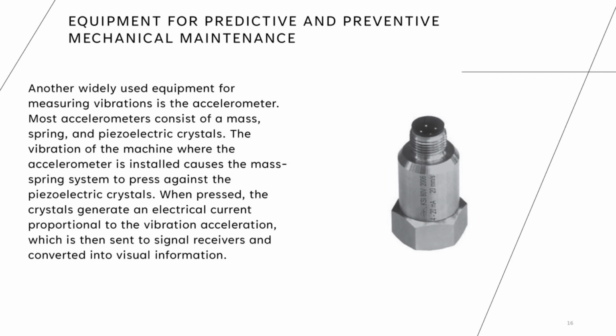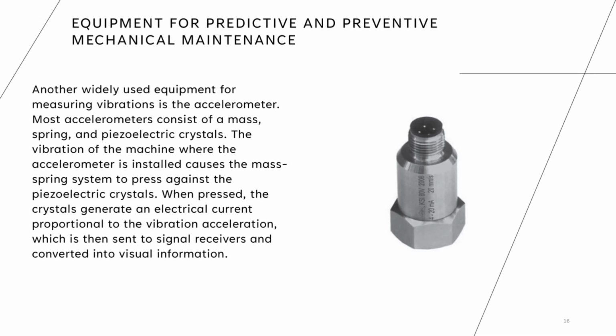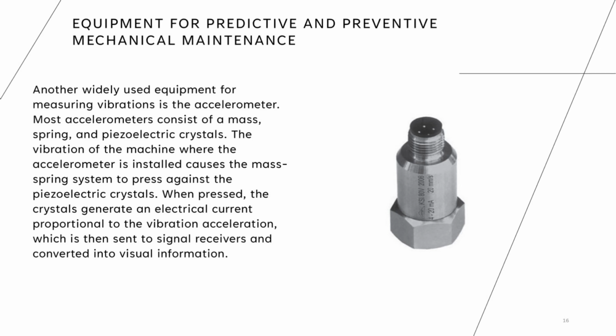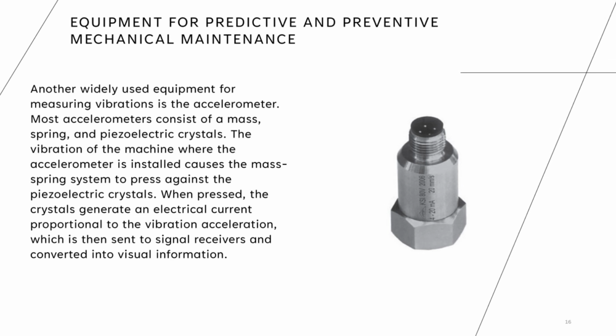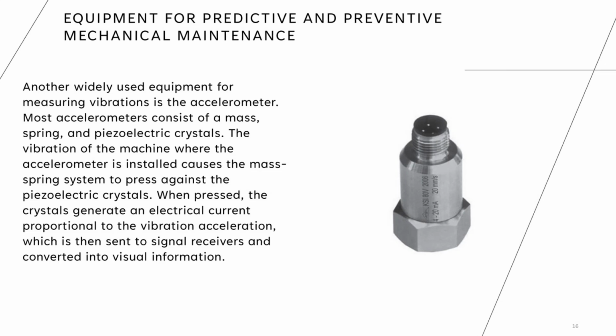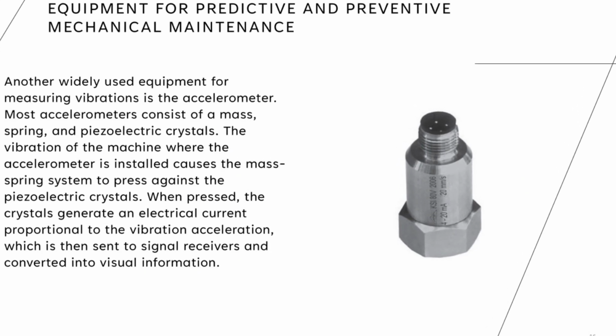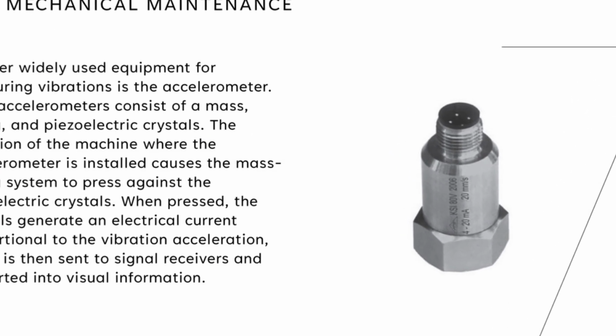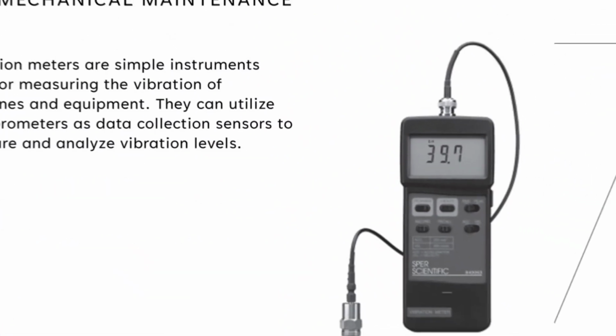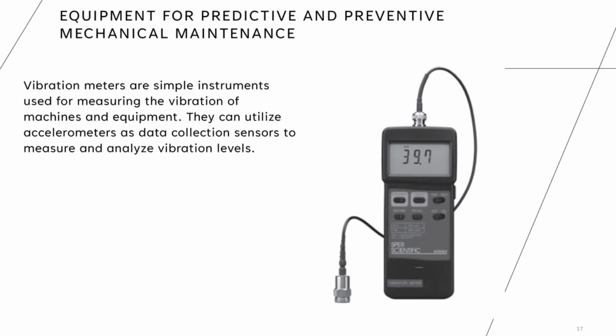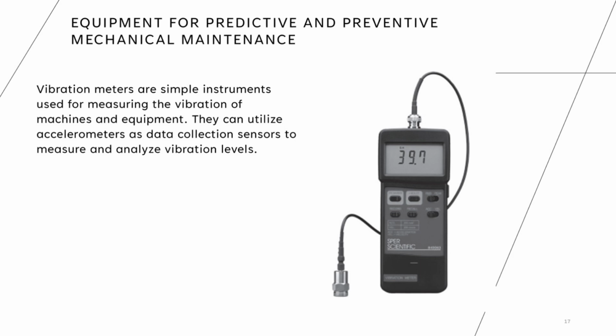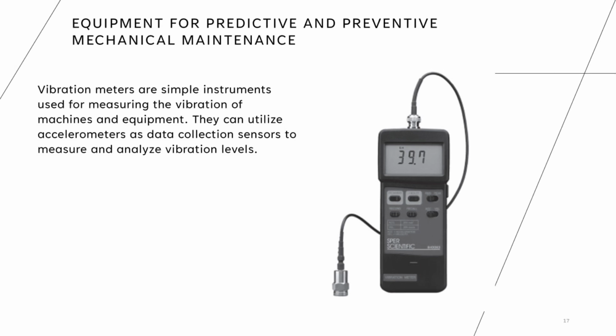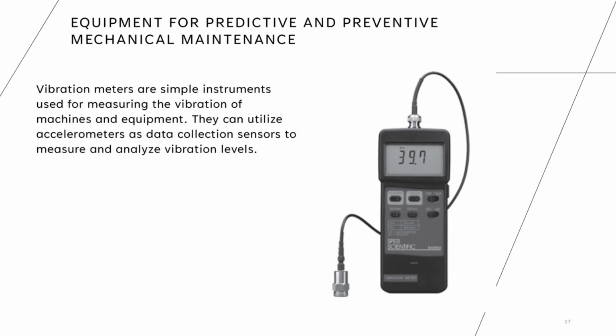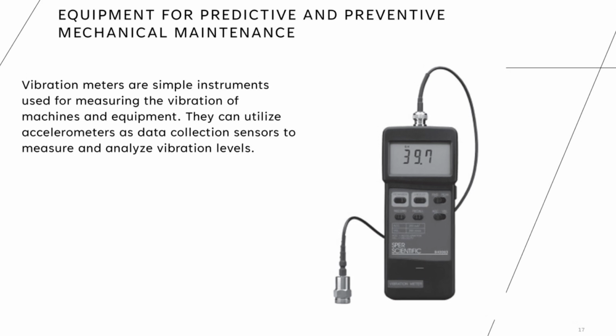Typically, accelerometers consist of a mass, a spring, and piezoelectric crystals. When the machine vibrates, the mass spring system presses against the piezoelectric crystals. This pressure causes the crystals to generate an electrical current proportional to the vibration's acceleration. The current is then transmitted to signal receivers and converted into visual information for analysis. Vibration meters are straightforward instruments designed to measure the vibration of machines and equipment. They often use accelerometers as data collection sensors to gauge and analyze vibration levels, providing insights into the machine's operational condition.